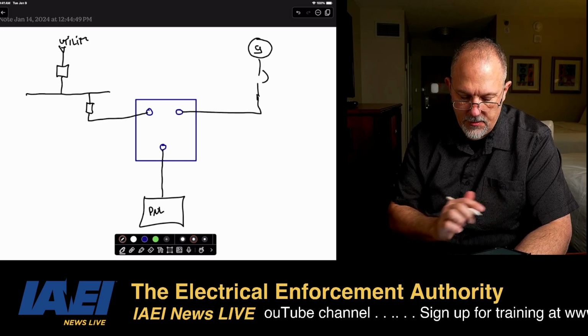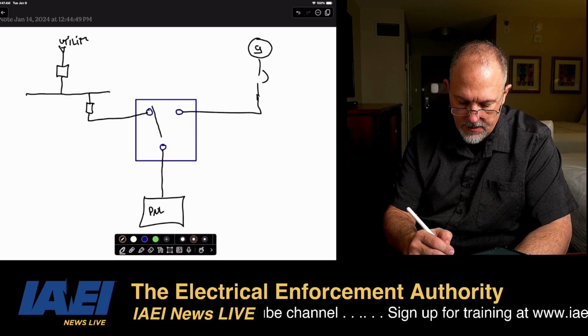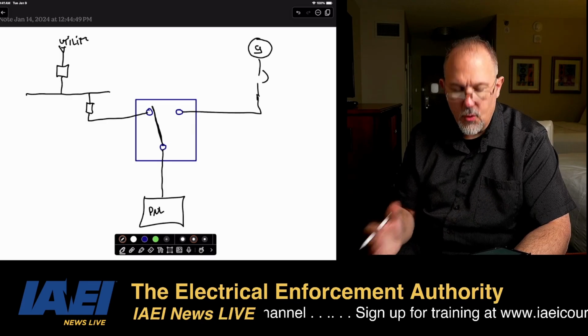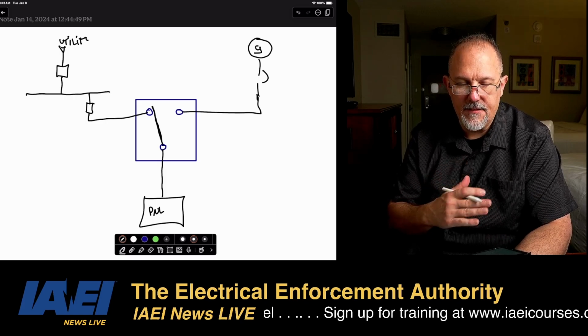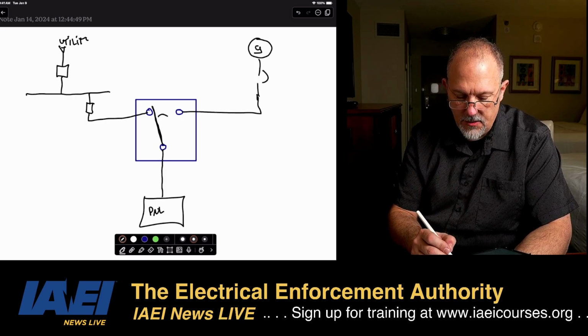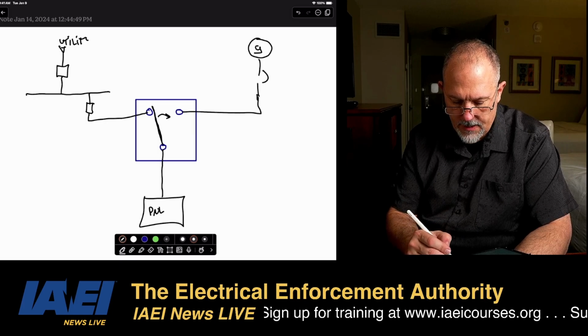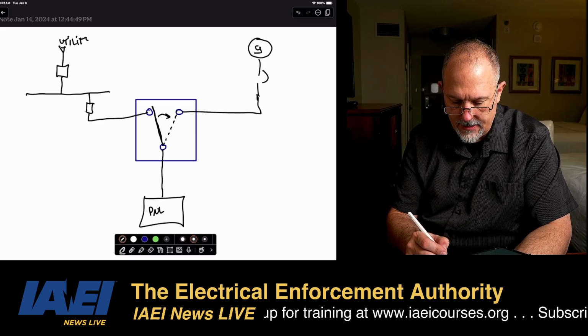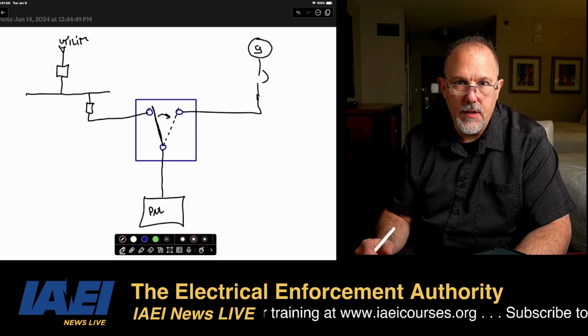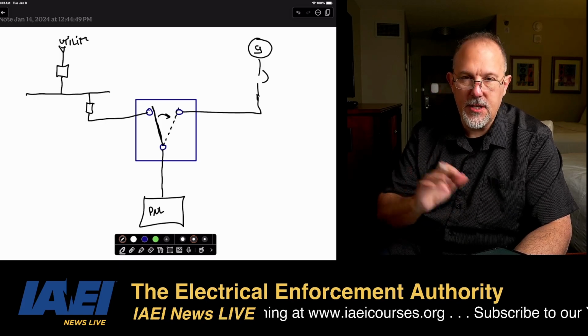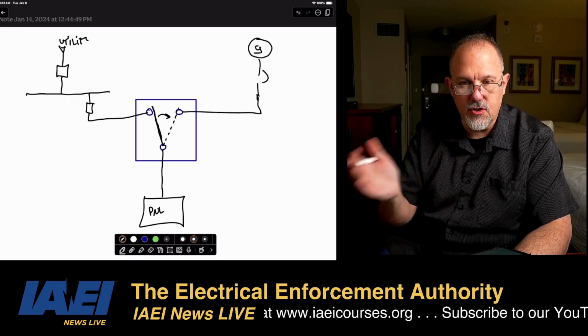So if I lose my utility, and let's say I do this, I'm normally on my utility side, and if I lose my utility, then that moves over. I'll just dotted line this one. How about that, huh? That moves over to the generator. And typically what will happen is you'll tell the generator to start, and then you'll transfer.